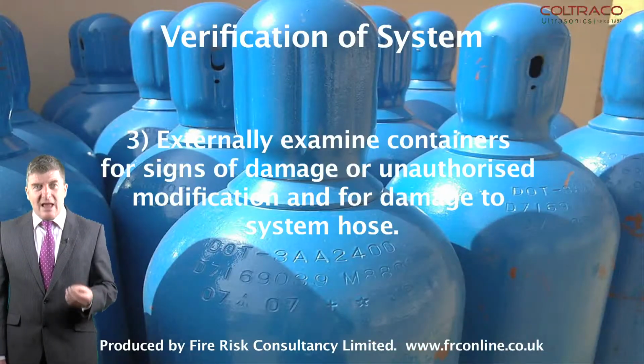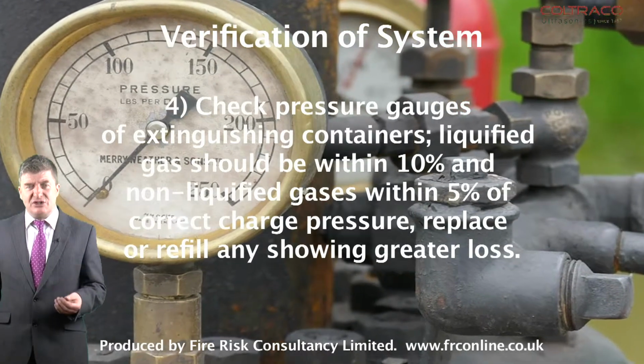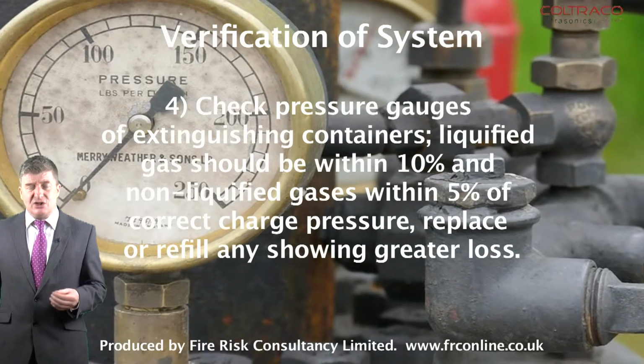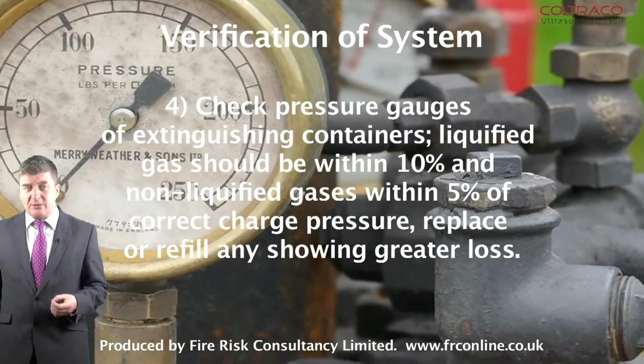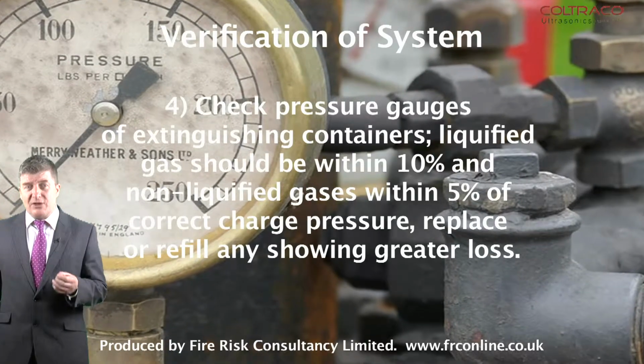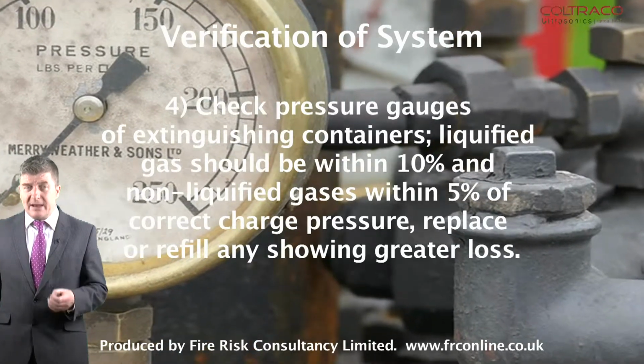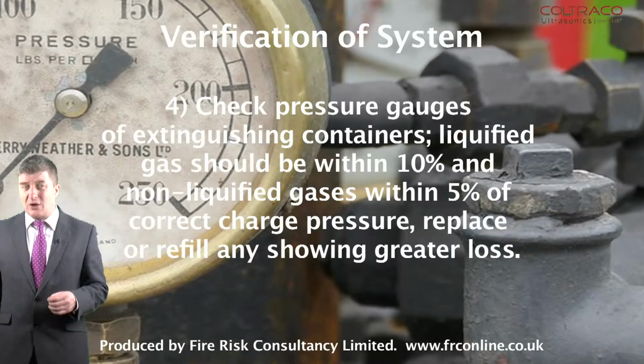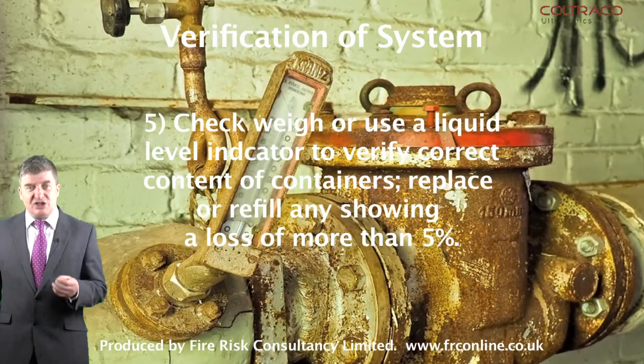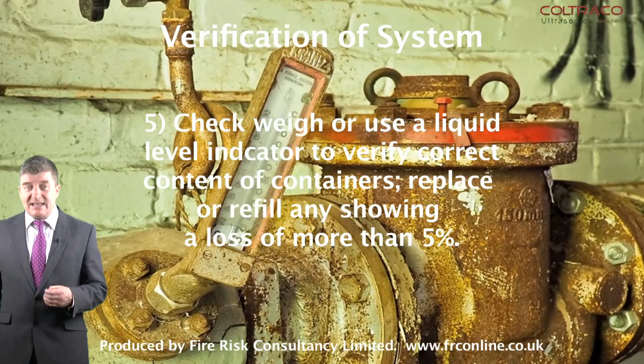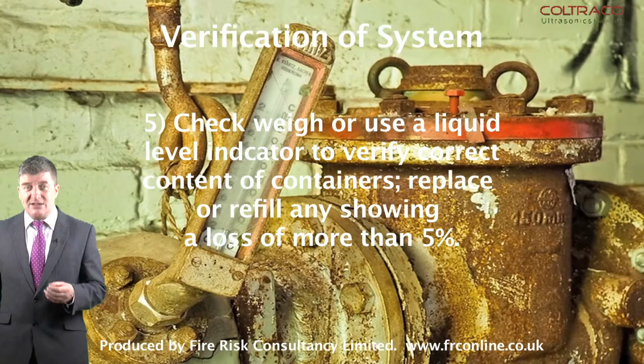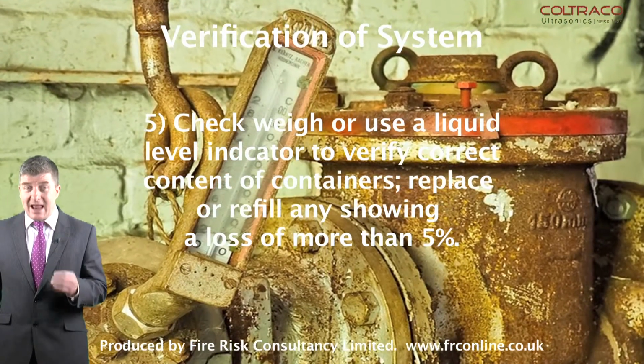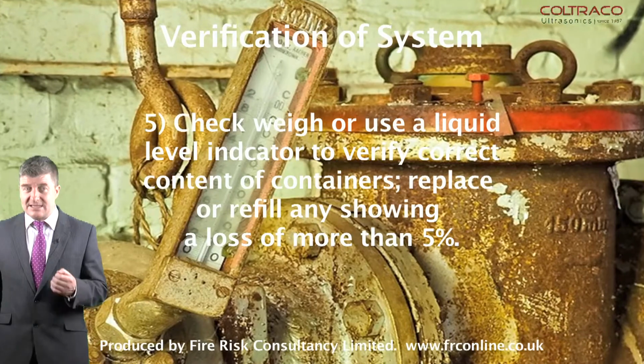And externally examine containers for signs of damage or unauthorised modification and for damage to system hoses. Check the pressure gauges of extinguishing containers. Liquefied gases should be within 10% and non-liquefied gases within 5% of the correct charge pressure. You should replace or refill any showing a greater loss than that. For liquefied gases, check, weigh or use a liquid level indicator to verify correct contents of the containers. Replace or refill any showing a loss of more than 5%.